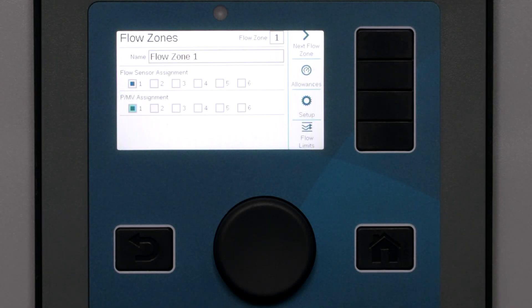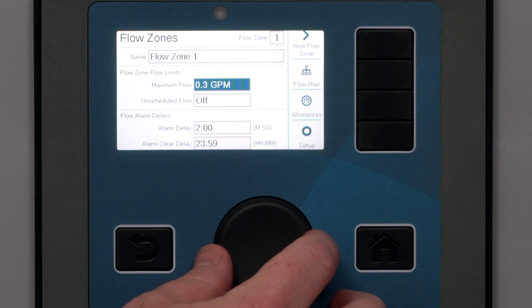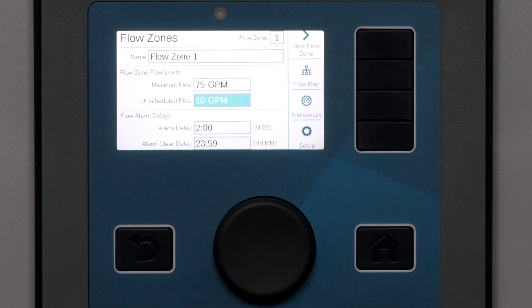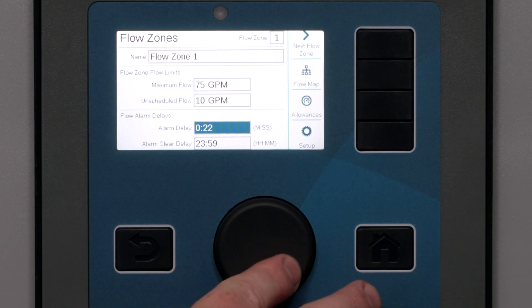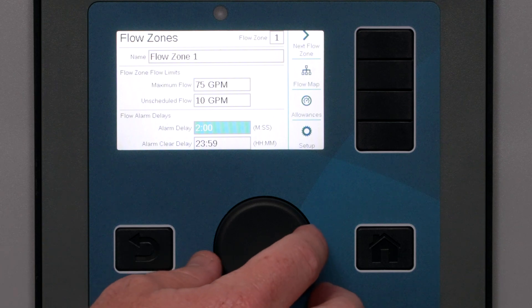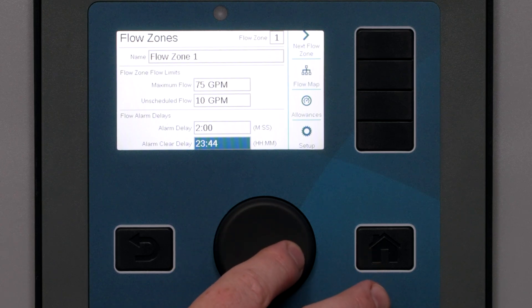Then click the soft key for Flow Limits. Here we can set an absolute maximum flow we will allow in this main line. We can also set a value for unscheduled flow — this setting will cause a flow alarm if flow is detected when nothing is supposed to be running. You can set a value to allow for manual irrigation from quick couplers and hose bibs, and it will ignore unscheduled flow up to that value and only alarm when it has been exceeded. The alarm delay sets the length of time this overflow must persist before it is treated as an alarm.